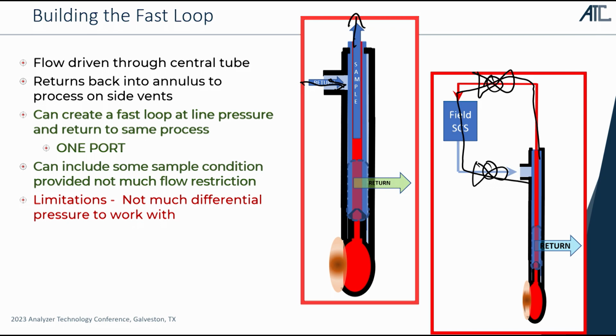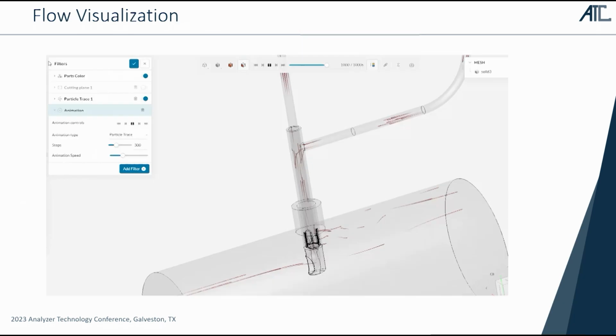The limitations that we have to consider with this is physics is going to determine how much differential we can actually create. Hopefully this animation is going to go. Let's see. There you go. So there's actually a computational fluid dynamics simulation of this probe in operation. Fluid flowing along the pipeline. So you can see the vortices that kind of show up around on the back side, but it drives flow up the center side, returns stuff back on the return side, and back into the process pipe.